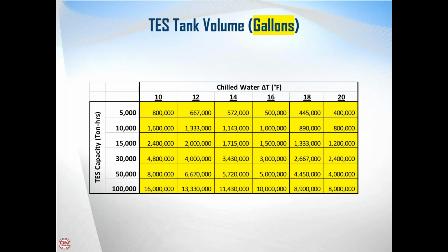This matrix is an example of the volume of water that would be needed in a thermal storage tank, depending upon the ton hours that were required to be stored of cold water and the chilled water temperature difference in the system. So on the left-hand side, the y-axis is the example of different amounts of ton hours in the tank. And across the x-axis is that chilled water difference between the supply and return water.